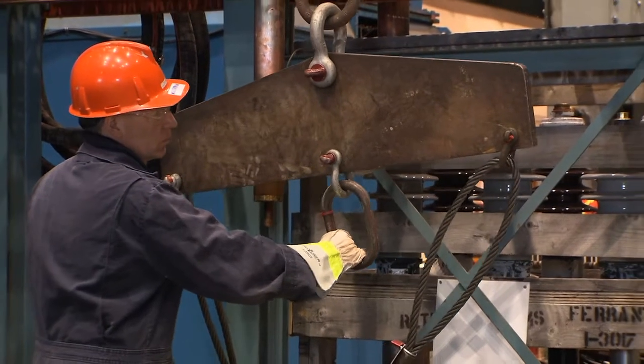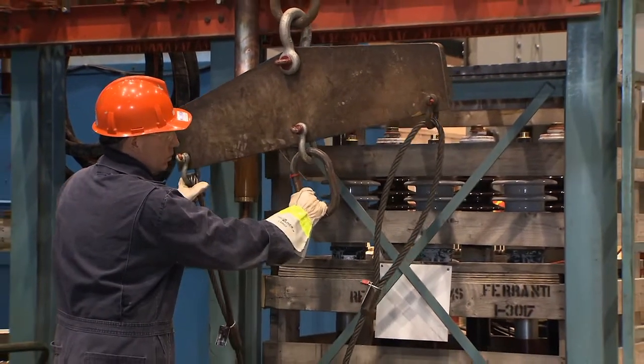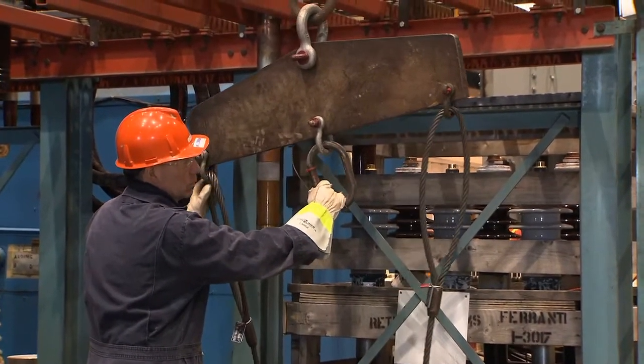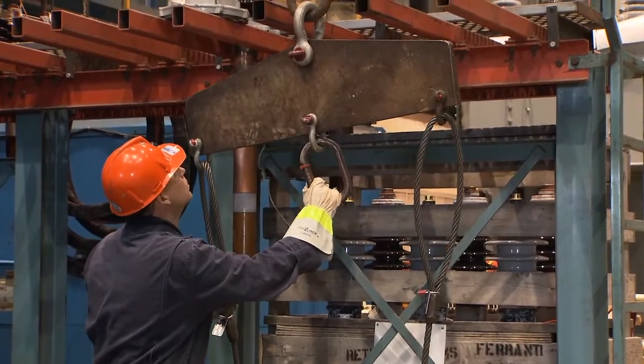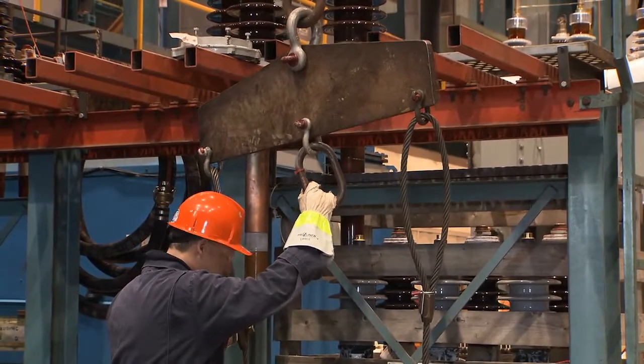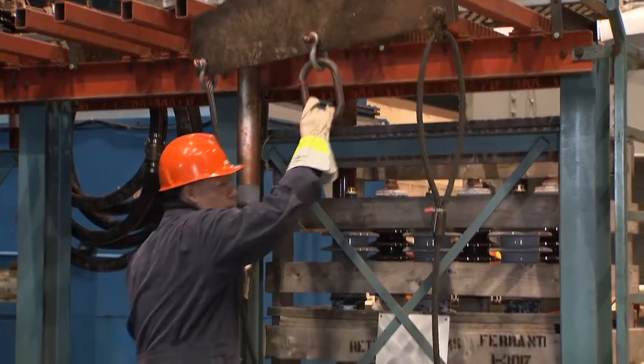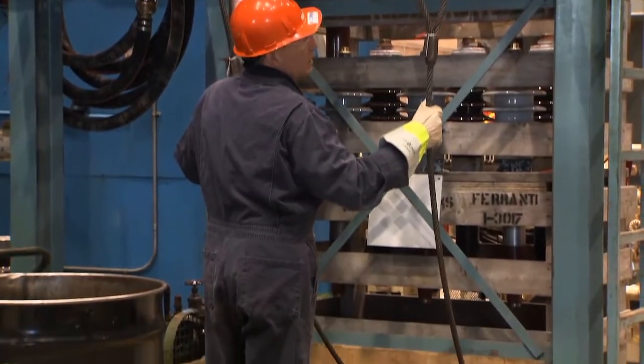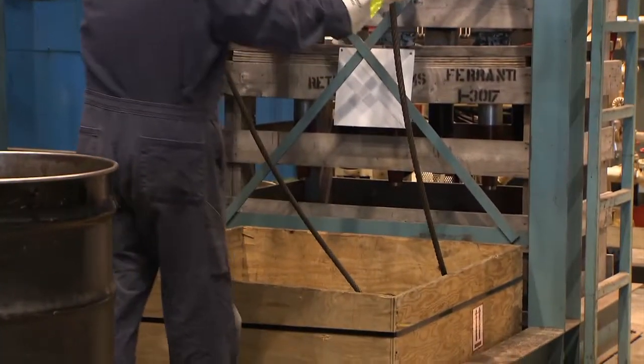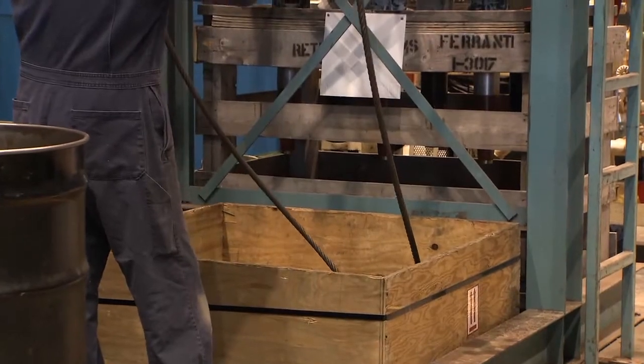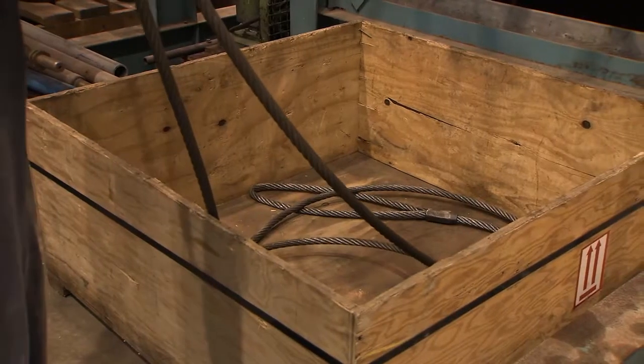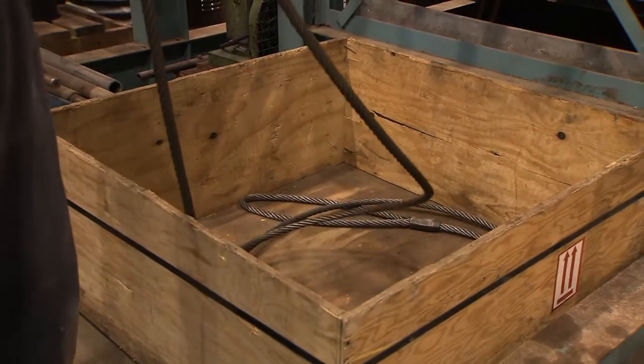Attach a multi-point lifting beam to the hoist hook on the crane, and then lower the hook above the wooden storage container for the cables used to lift a bushing from a transport carrier. Attach the ends of the lifting cables to shackles on each end of the lifting beam, and begin lifting the beam to remove the cables from the container. Continue to lift the metal cables up and out of their storage container.